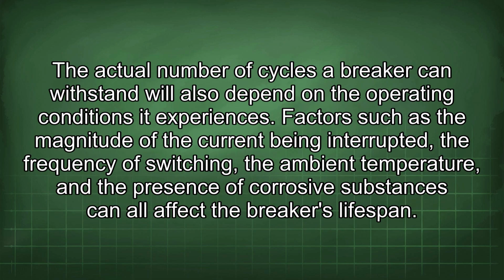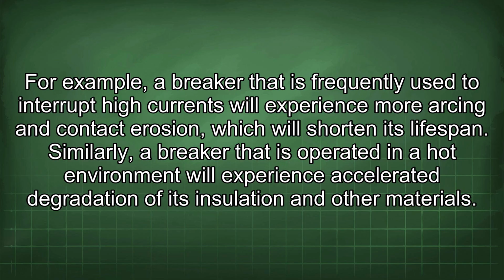degrade. The actual number of cycles a breaker can withstand will also depend on the operating conditions it experiences. Factors such as the magnitude of the current being interrupted, the frequency of switching, the ambient temperature, and the presence of corrosive substances can all affect the breaker's lifespan. For example, a breaker that is frequently used to interrupt high currents will experience more arcing and contact erosion, which will shorten its lifespan.